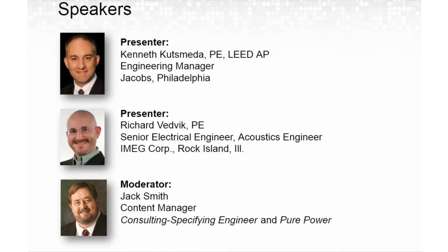When you're paralleling multiple generators, especially generators by different manufacturers, you have an opportunity to have harmonic content that is not necessarily cooperative. For example, if you have parallel pitches because you happen to not have neutrals in the system, and it allows you to parallel generators to different pitches, you can end up with more harmonic content than you would normally see. In my experience, at certain times, depending on the nonlinear load and the harmonics in the rest of the system, the UPS doesn't want to connect to that.